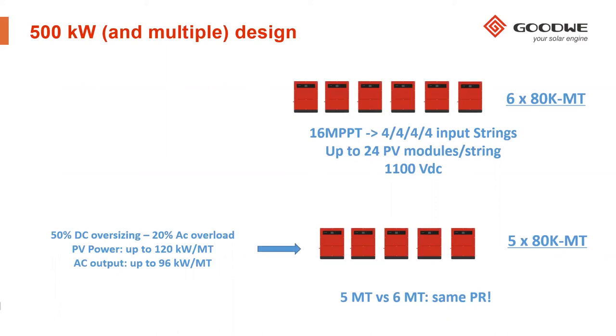For sure, what is necessary is to check site by site the temperature conditions. It's clear that in extremely hot situations, you can also have some derating, even though our system is designed to work without derating in the range minus 30 to plus 50 degrees ambient temperature. So just to summarize, our standard proposal is for 6 inverters of 80K, but please consider also this combination, which gives you a big advantage in terms of cost. And our team, Alessandro and Trifonas, can support you in the design of this system to check if this is compatible with your local situation.